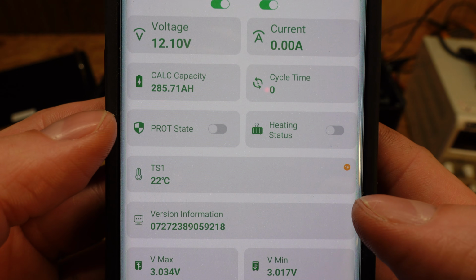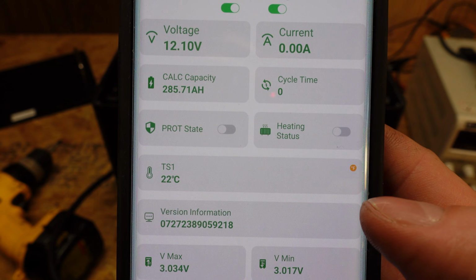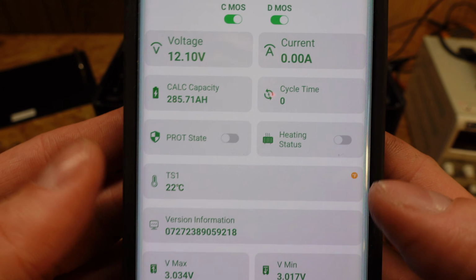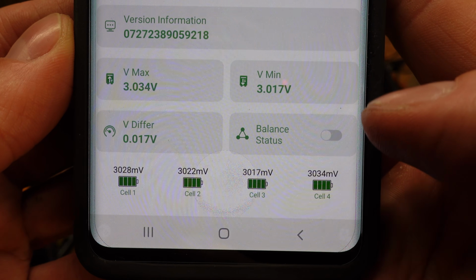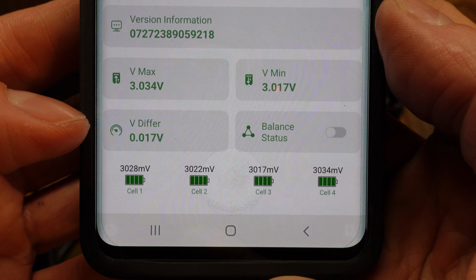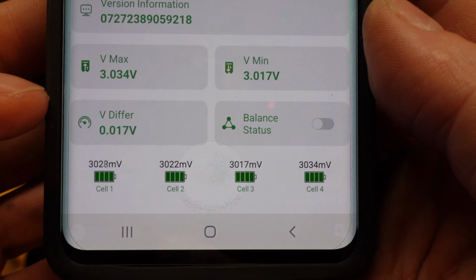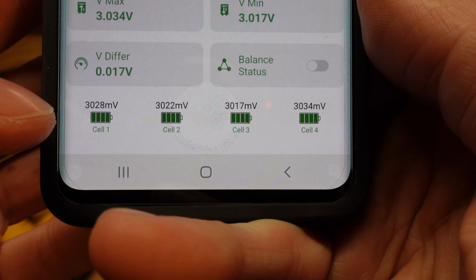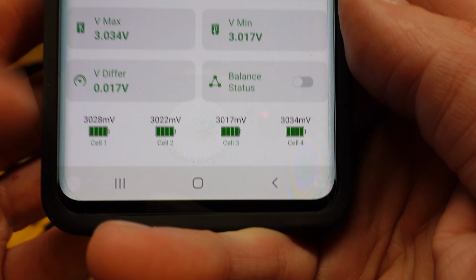We can see indicators for the protection status, that's over or under voltage protection, discharge protection, things like that. We also see an indicator for balancing status and the voltage differential. We're sitting at a difference of 0.017 volts per cell. And lastly, we can see the voltages of all 4 cells there at the bottom.